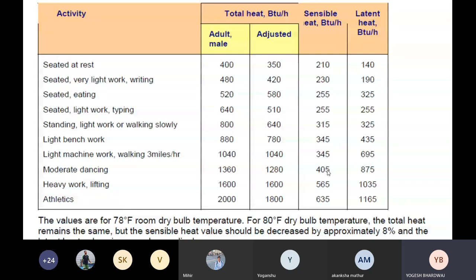Now heat ingress due to infiltration. So infiltration means the air which is coming through leakages unintentionally into our room, because that air is hotter. That's why we need to evaluate the heat ingress in our room because of this air. So in typical building, air leaks into or out of space through doors, windows, or small cracks in the building envelope. Air leaking into a space is called infiltration. During the cooling season, when air leaks into a conditioned space from outdoors, it can contribute to both sensible and latent heat gain into the space, because the outdoor air is typically warmer and also more humid.